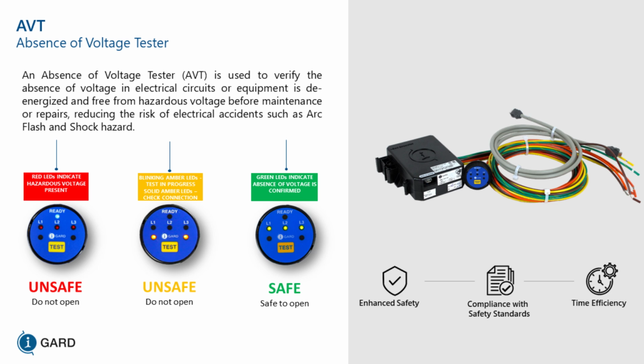So this particular device gives you 3 red LEDs. This is a permanently mounted device connected to every disconnect switch that you want to consider. It has 3 indicating red lights to indicate that it's unsafe. When you shut off the switch, you press the test button. When you press the test button, it's going to measure the voltage phase to phase and phase to ground. It's going to look at AC voltage and DC voltage, and more importantly, it's going to check to make sure that it's functionally working properly, has an internal protection circuit, and is connected to the phases of your system.